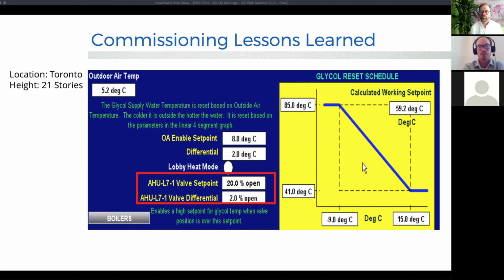That was their countermeasure for this, and they actually had a lobby heat mode—you can see that just above the red box—which was activated again once it went beyond 20%. So there are lots of folks who come up with strategies like this, but in this particular case it clearly did not work. It didn't really make people in the lobby more comfortable, and it used an excessive amount of natural gas on the boiler plant. It clearly didn't have the impact they were looking for.